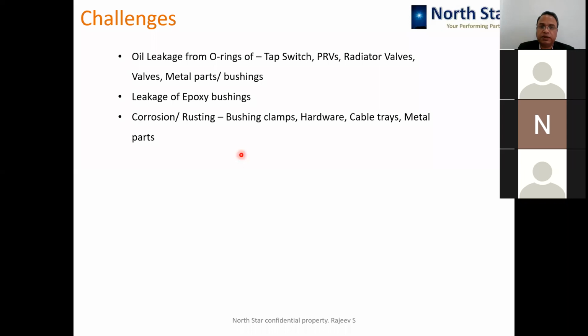Corrosion, rusting, bushing clamps, hardware, cable trays, metal parts - all these things get rusted in due amount of time. Coating and deteriorated powder coated panels are notorious for getting rusted because of improper process or wrong selection, since powder coated equipment is not suitable for highly corrosive atmosphere. So if you are doing powder coating for something going to a location where salty atmosphere is there, your powder coating is going to give you trouble.